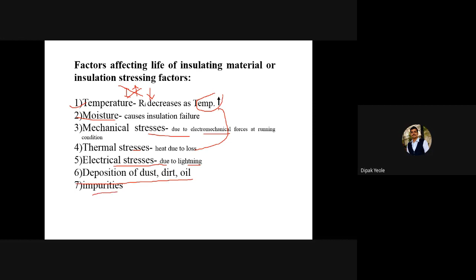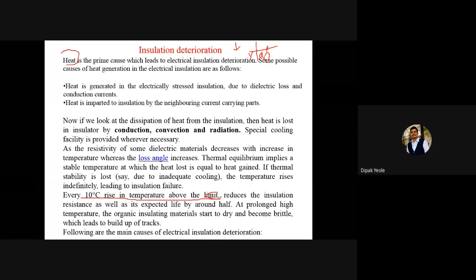Yes. So you can see, for every 10 degrees Celsius rise in temperature above the limit, we have seen the class as well as the temperature. If we are interested in the Y class, then obviously we have to keep the temperature at 90 degrees. But if the temperature goes beyond 90 degrees, let's say 100 degrees Celsius, then obviously the insulator starts deteriorating its property and the life of it decreases to nearly half.